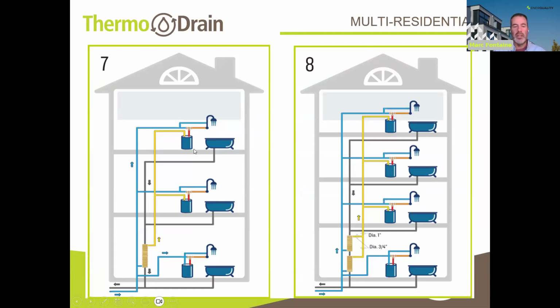So you'd have 2 out of 3 dwellings providing drain water heat to the ThermoDrain unit. And the preheated water would go back to the hot water heaters of the dwellings above. So this is how you would recover the heat. Imagine a building with 6 dwellings: you have 1 unit at the bottom of each stack. So 2 drain water heat recovery units for the whole building, and you have 4 out of 6 dwellings being serviced by this device.